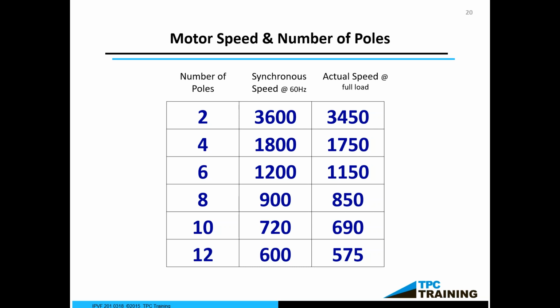We have to be able to calculate synchronous speed and rotor speed, and there's a little bit of math involved. It's not that big a deal, but we would not want to exceed 3 to 5%. So there's a few calculations going to be involved. There's actually a handful of calculations with regards to these particular drives. Synchronous speed and rotor speed, not to exceed 3 to 5%.